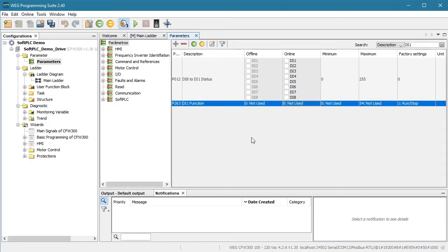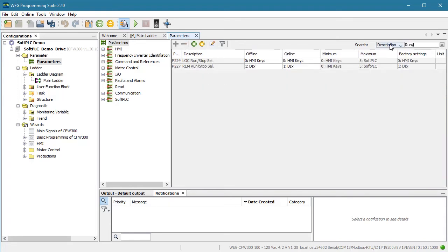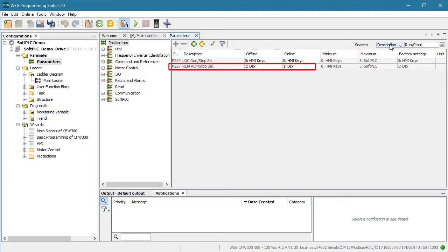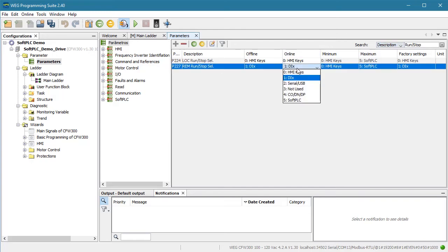Remember, this write happens automatically because we are connected to the drive. Because DI1 was defaulted to control run stop, something was probably expecting to use it. Let's search the parameter list for run stop. Ah, look at that – the remote run stop was planning to use DI1 as the run stop control. Now, we don't have to change this. It's not going to work anyway since we turned it off in parameter 263. But it's nice to go ahead and change it anyway so in the future when others are looking at your setup there won't be any confusion. Let's change the remote run stop to be controlled by the HMI just to get it out of the way.